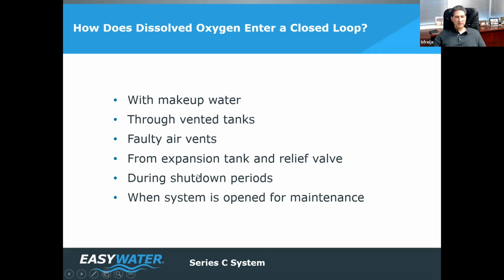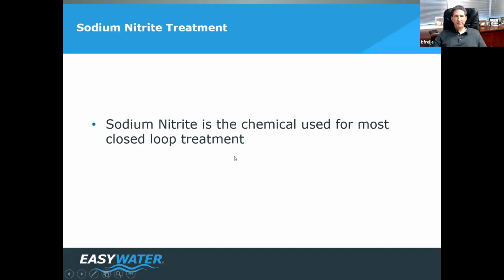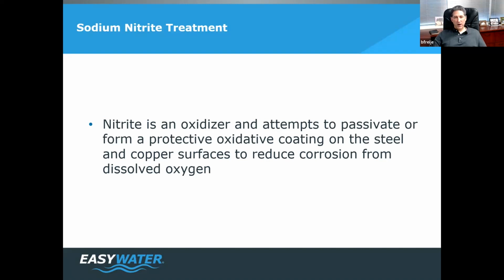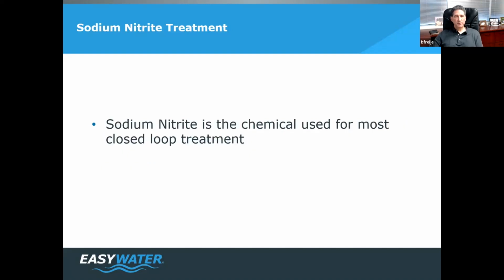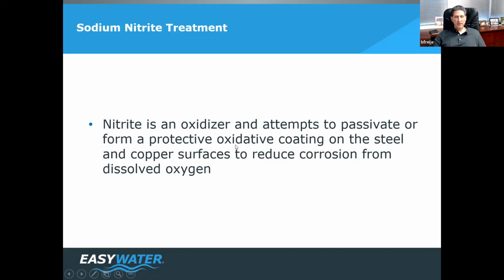All these places. So you specify a pot feeder. What do they put in that pot feeder? Well, over 95% of all chemically treated closed loops are treated with sodium nitrite. So how does sodium nitrite work? Well, it's corrosive. It's an oxidizer. It attempts to put a protective oxidative barrier on all the steel and copper surfaces to reduce corrosion. It literally uses corrosion to reduce corrosion, a little backwards, frankly, in my opinion.